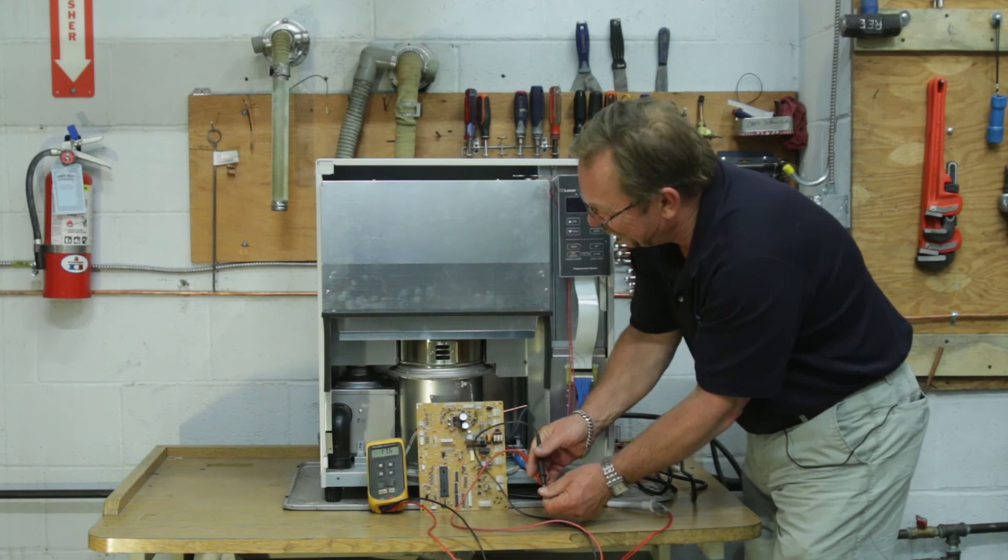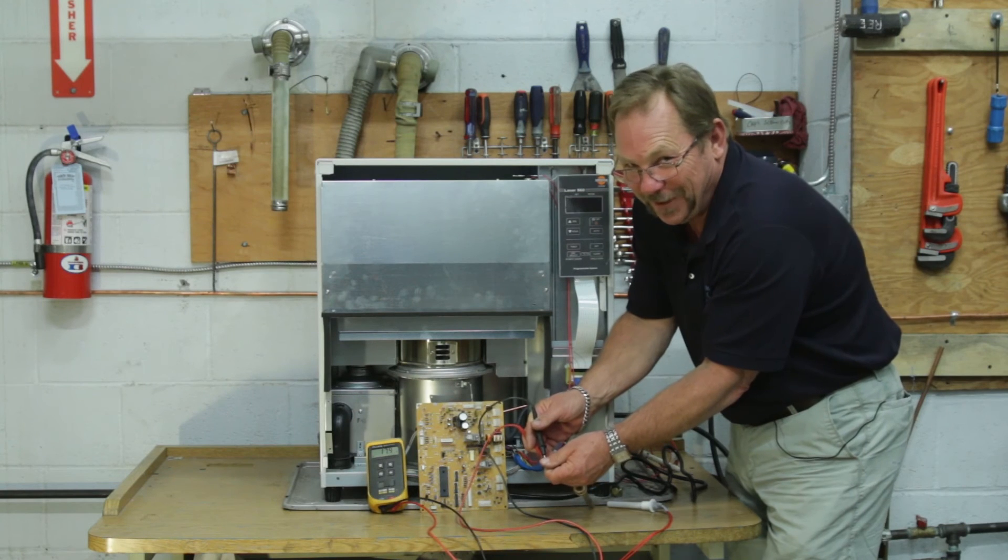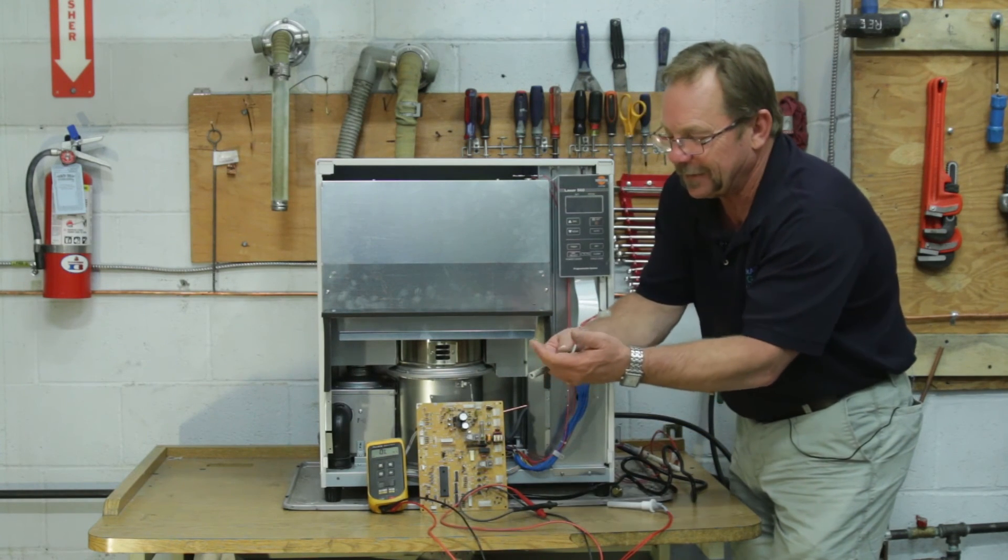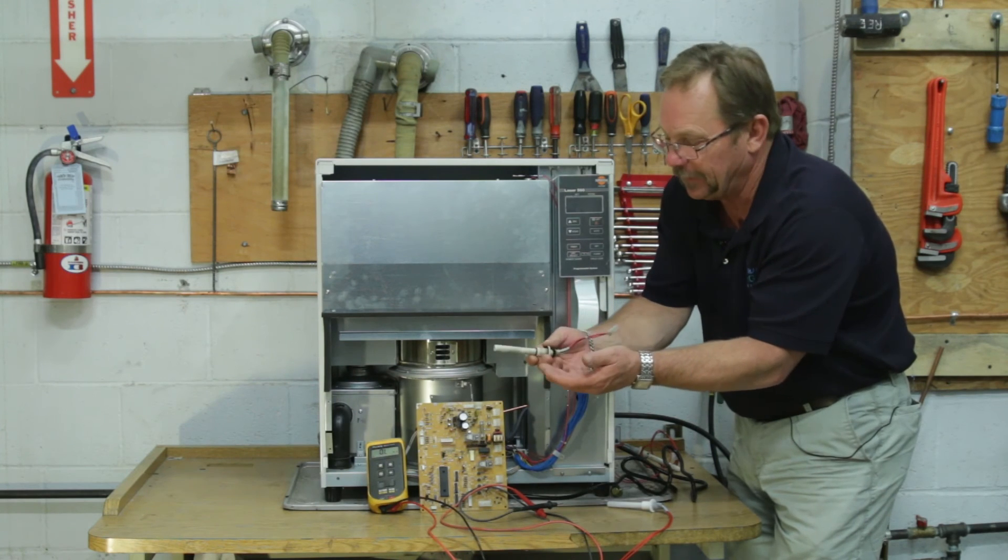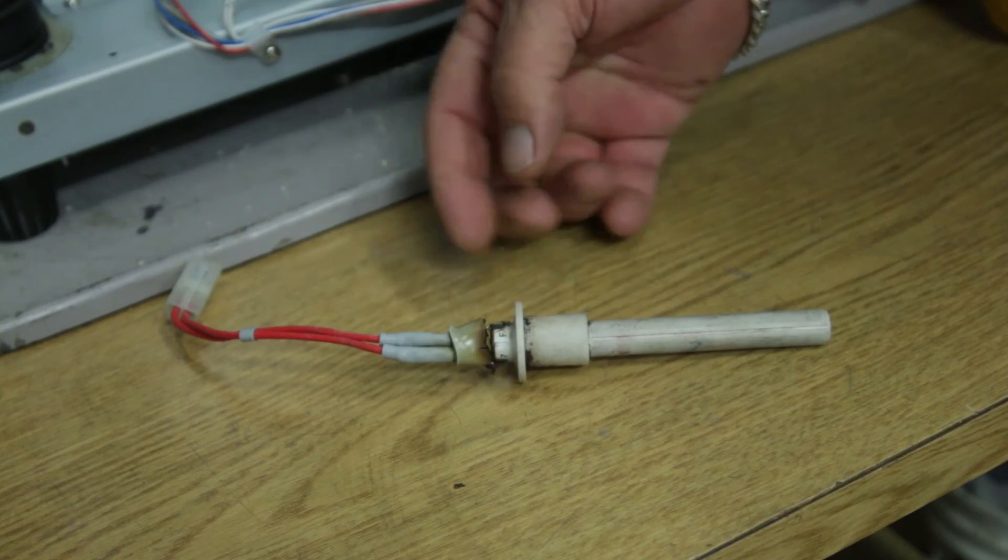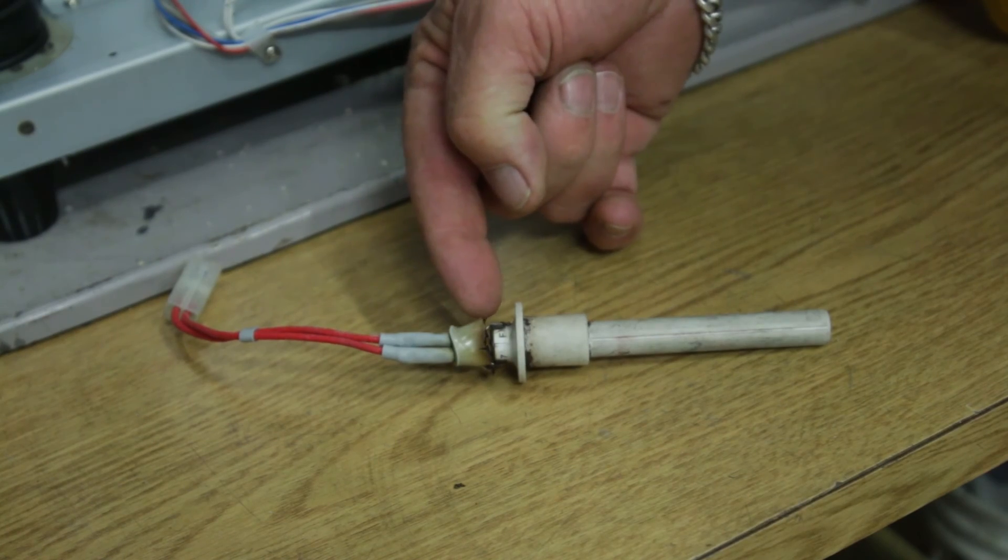This igniter is reading within the factory specifications. So we've checked the circuitry inside this igniter, which is good, but yet this igniter is not a viable igniter because of the back side right here.